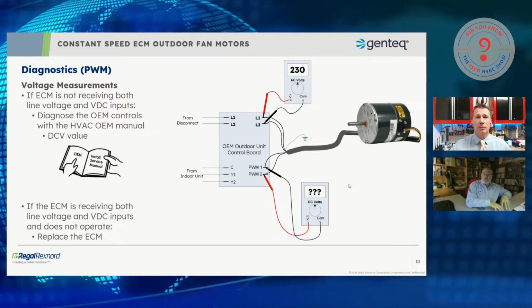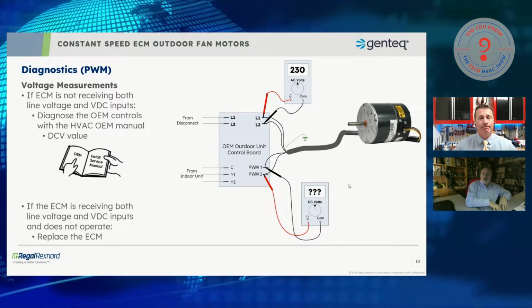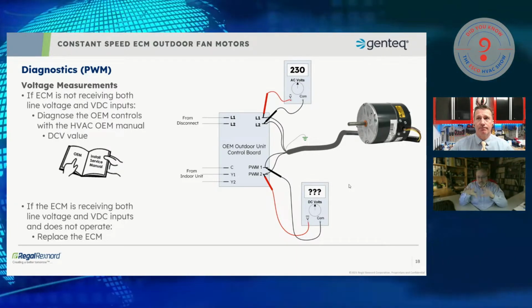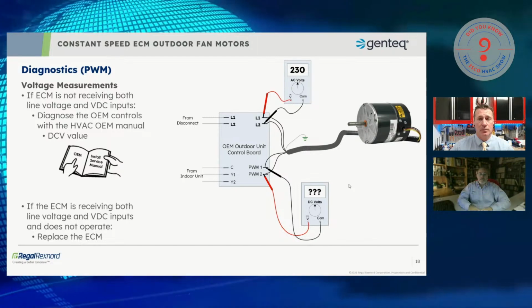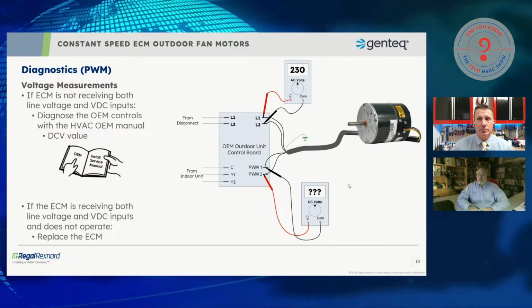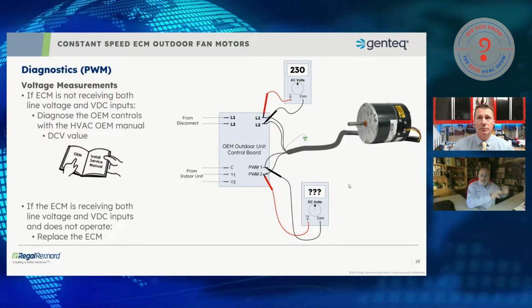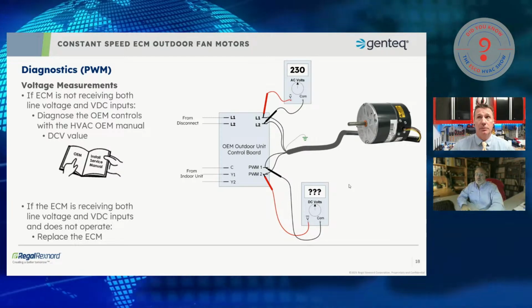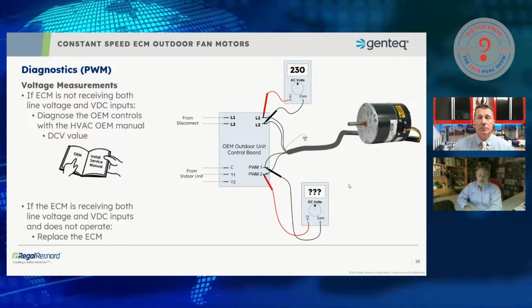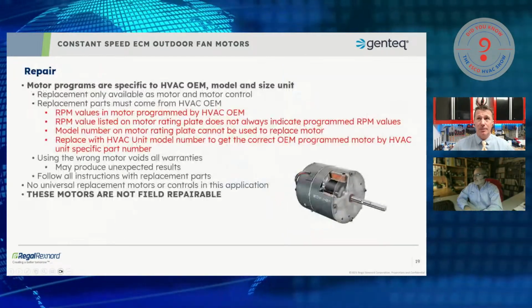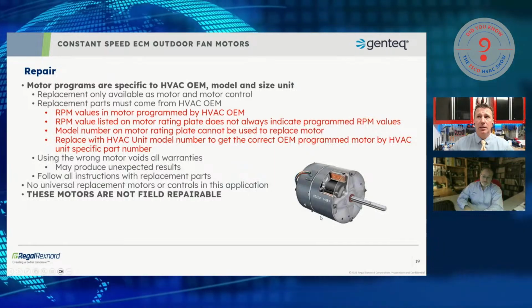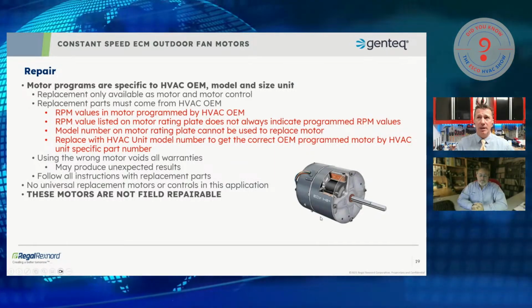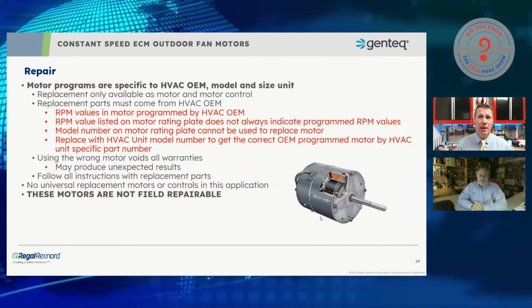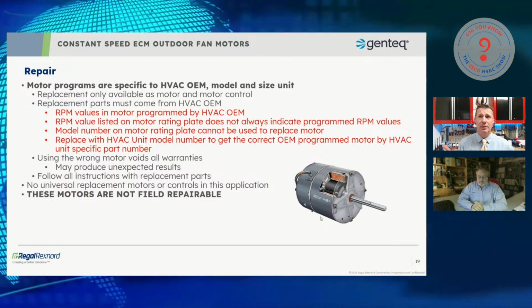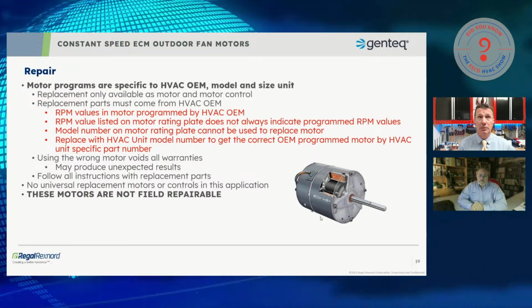They could run that motor at a different RPM value, even though it looks like the same motor, same horsepower, could even be the same Genteq model number on that motor. They could send a different PWM signal to that motor because it's in a different application. Different prop, even just a prop angle. I mean, I've seen applications where we've had a manufacturer change suppliers of blades, and then in the middle go, oh, what should we do?